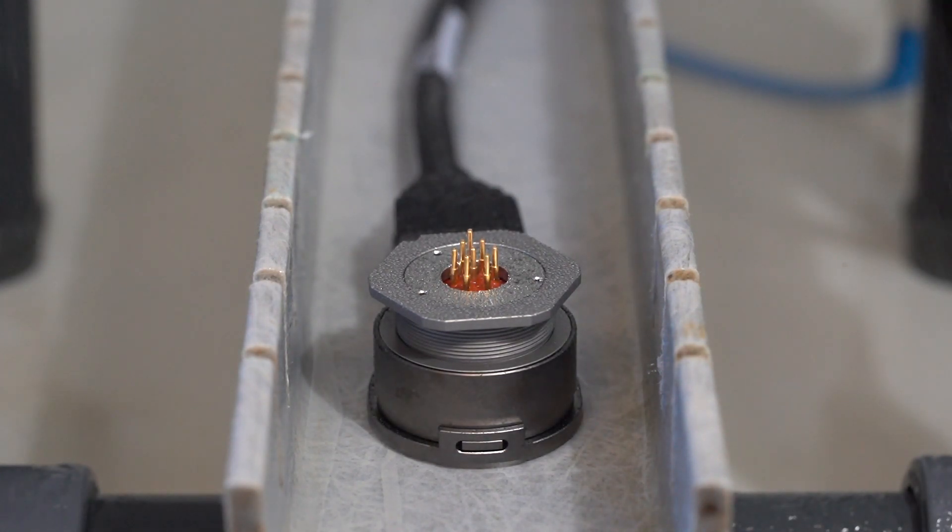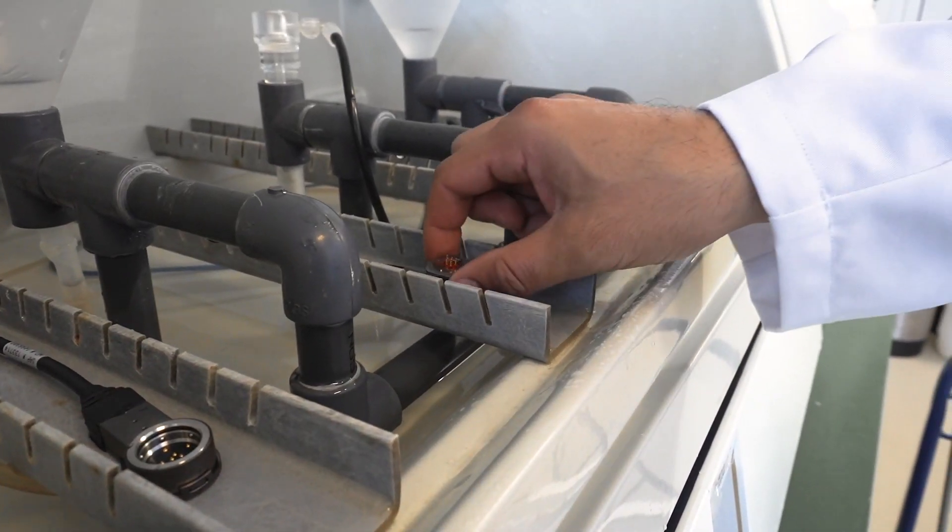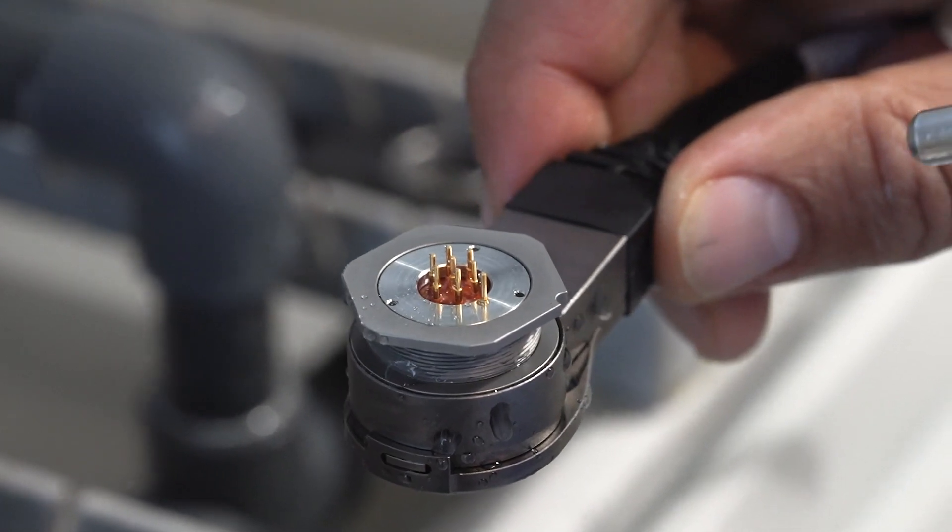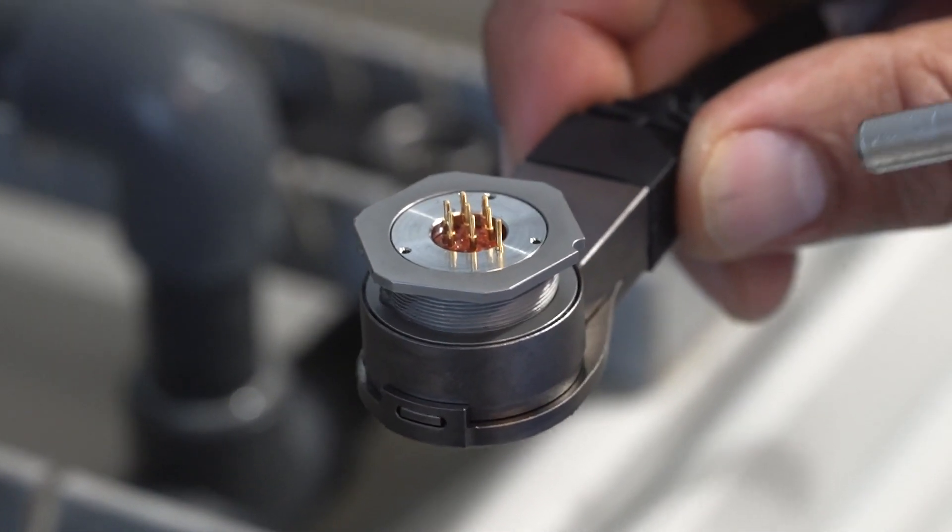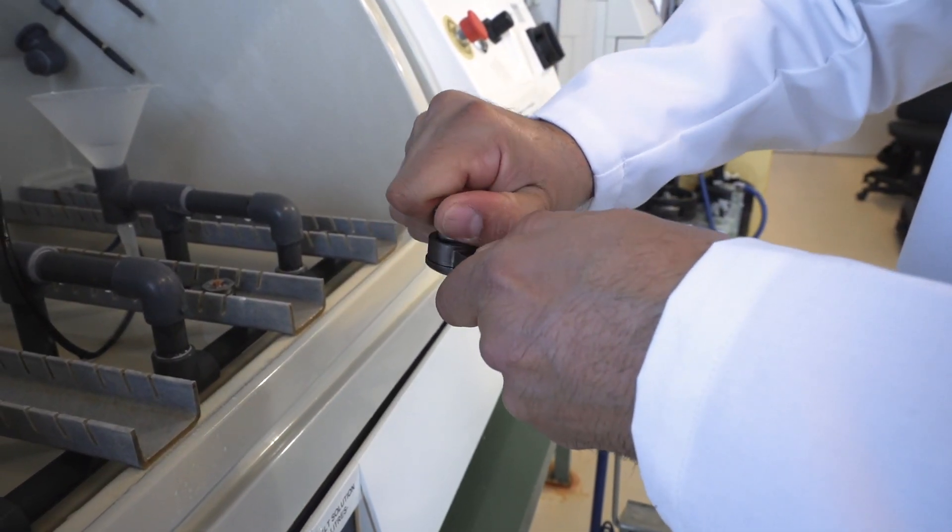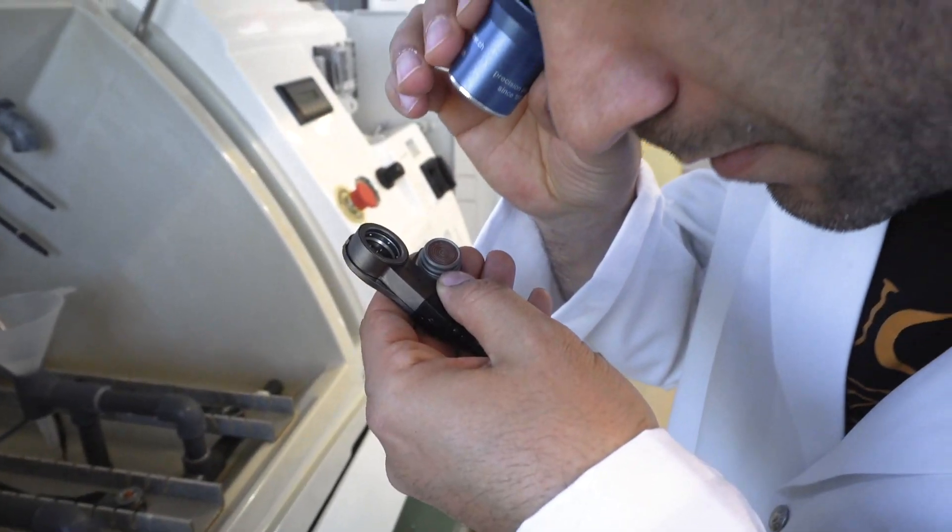After a thousand hours, the connectors are removed from their supporting racks and dried. Visual, electrical and mechanical controls are performed after the test. Cosmetic changes may appear over time without impacting mechanical or electrical functionalities.